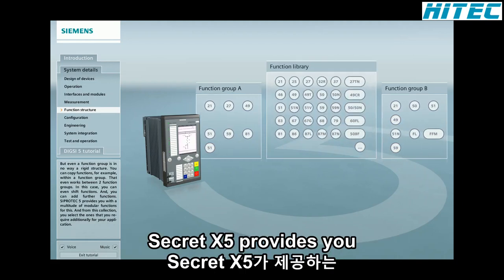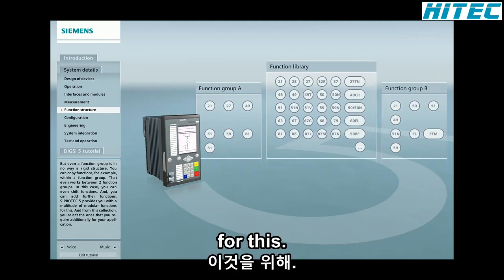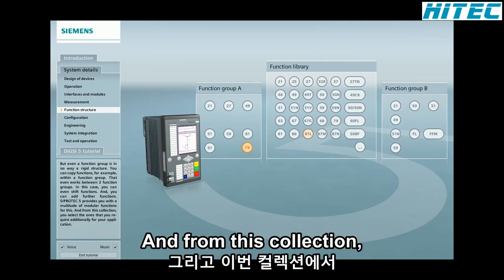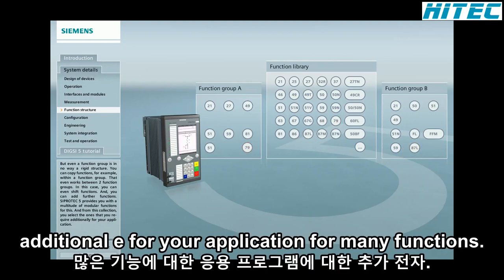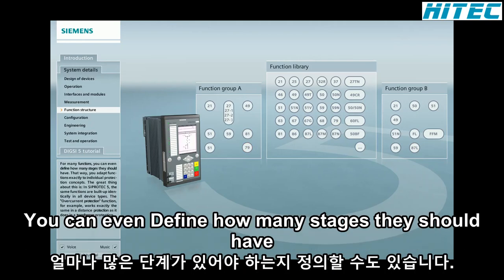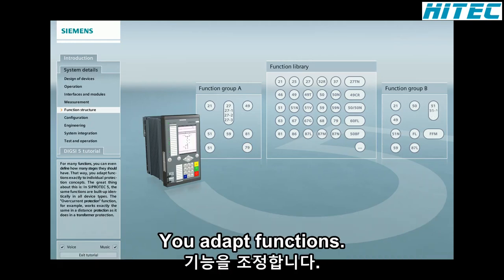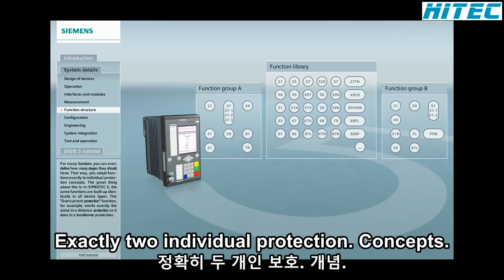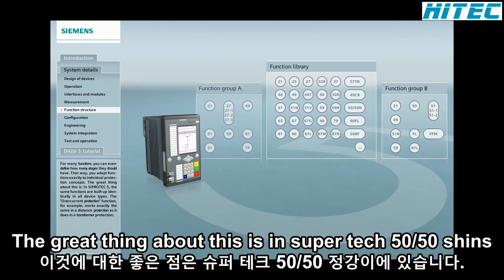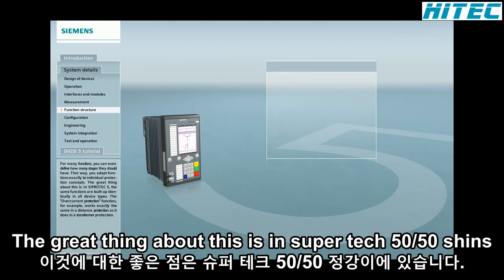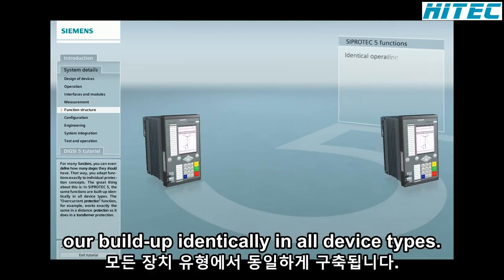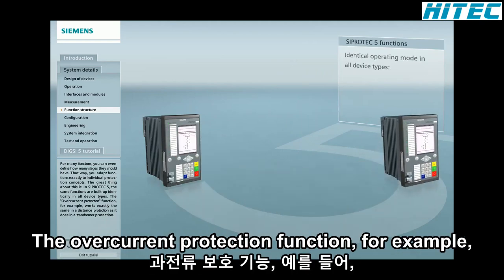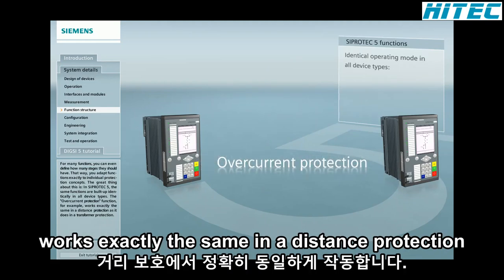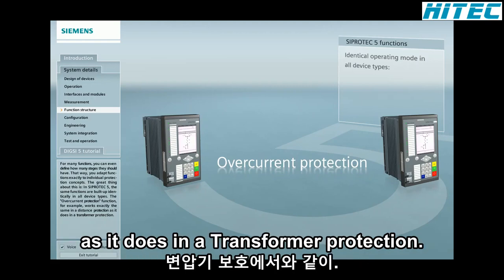SIPROTEC 5 provides you with a multitude of modular functions for this. And from this collection, you select the ones that you require additionally for your application. For many functions, you can even define how many stages they should have. That way, you adapt functions exactly to individual protection concepts. The great thing about this is, in SIPROTEC 5, the same functions are built up identically in all device types. The overcurrent protection function, for example, works exactly the same in a distance protection as it does in a transformer protection.